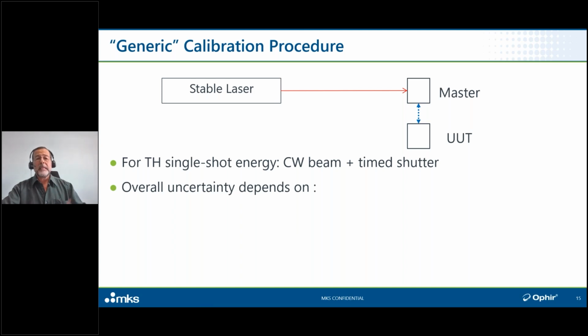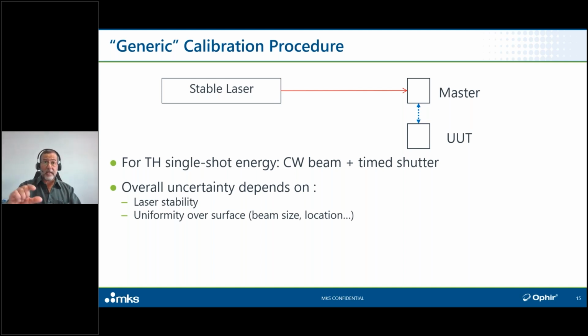The overall accuracy, the overall uncertainty in this whole calibration process depends on a bunch of different factors. Just how stable that laser really is, uniformity over the surface of the master and over the sensor being calibrated, and that could interact with the beam size and the beam position to introduce another variability in the calibration, so we need to control that.